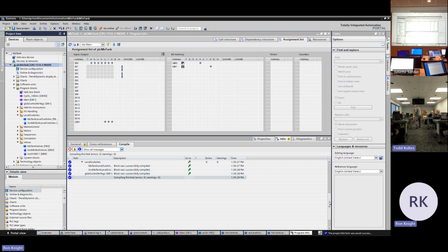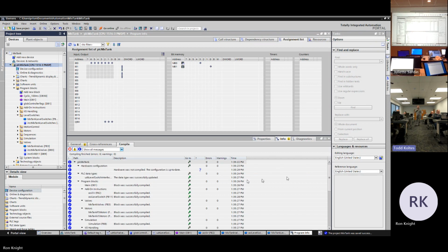Ah, okay. That's a kind of generic warning. That doesn't stop you from downloading, executing code or anything like that. Typically we don't want to leave blank passwords. Imagine someone being able to go up to your display in the field and put the PLC in program mode. That would be like leaving the key switch on the front of the PLC on a ControlLogix. So it's just saying you really should put a password there.